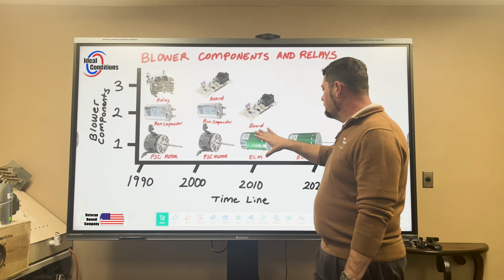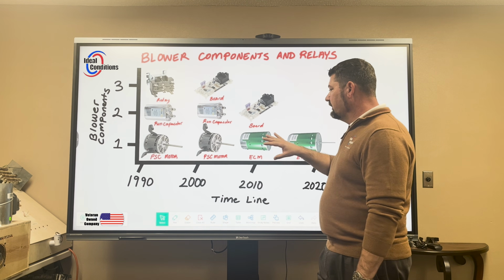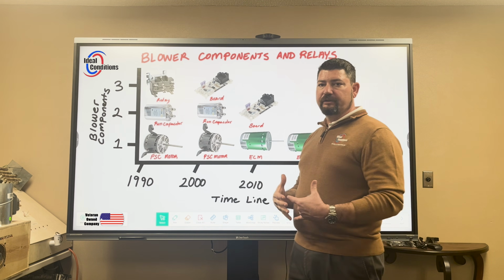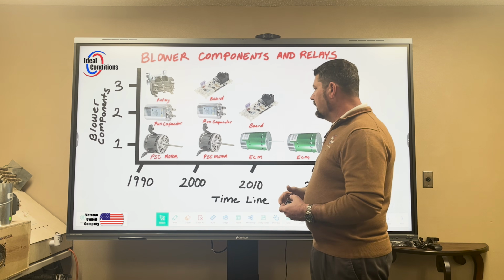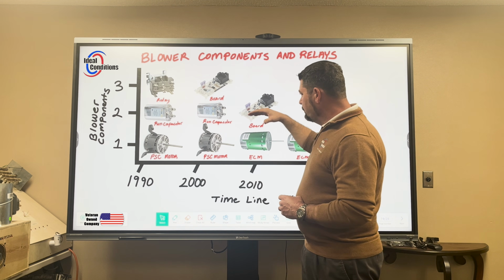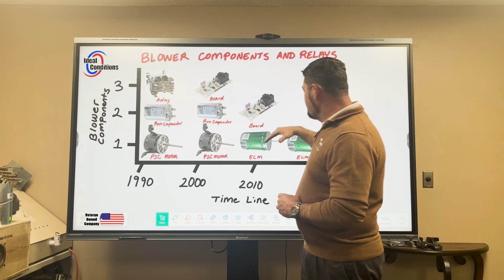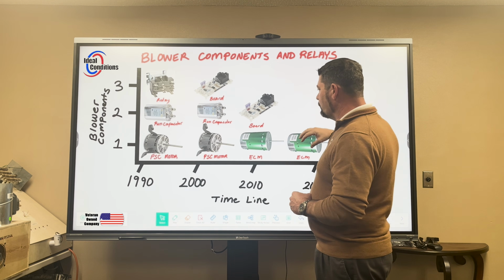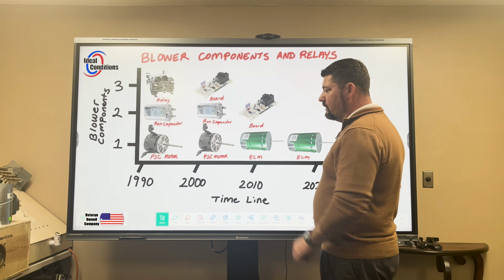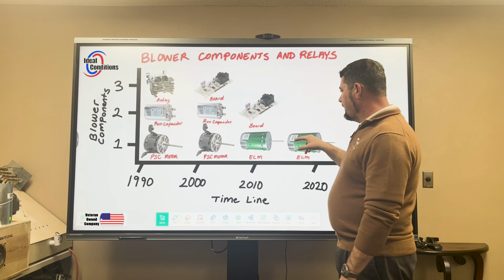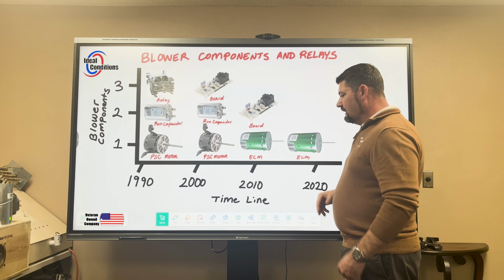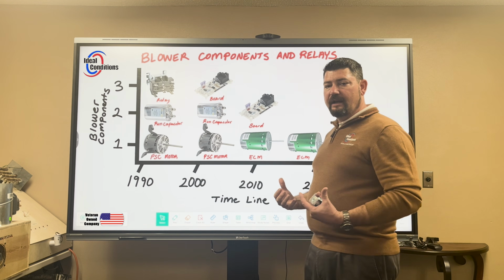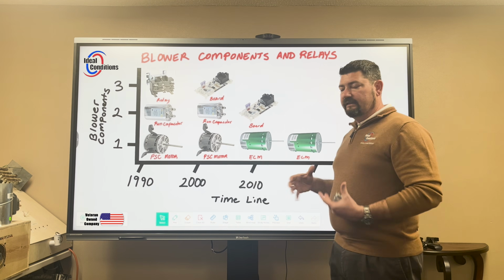When we get to the ECM, that one component's gone, because inside that module they already have those capacitors built in. They started to integrate the relays inside the motors as well, so now these modules are pretty much a one-stop shop, with all these additional components built inside. So if it fails, all you can do is replace that one part.